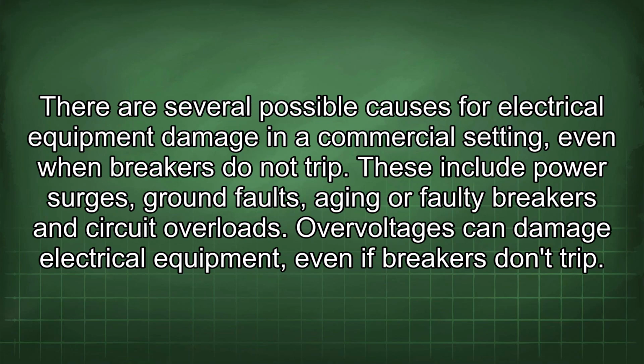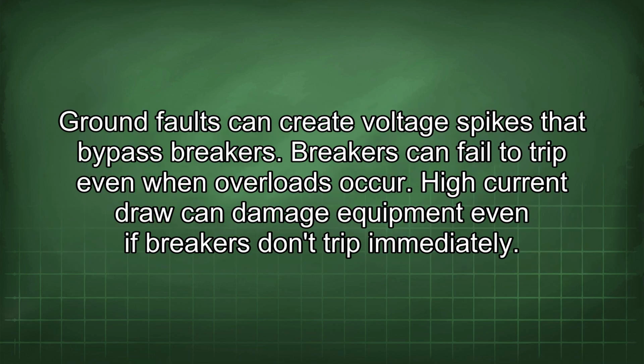There are several possible causes for electrical equipment damage in a commercial setting, even when breakers do not trip. These include power surges, ground faults, aging or faulty breakers, and circuit overloads. Overvoltages can damage electrical equipment, even if breakers don't trip. Ground faults can create voltage spikes that bypass breakers.